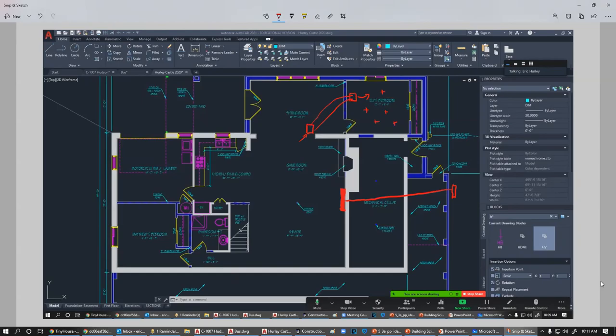All right. So I've got that inch space under here. I do have some air flowing through here, and I do have some air exchanges in here. This is not passive. There's an inline duct fan in here. In the summertime, it comes on every 30 minutes and shuts off for every 30 minutes. In the wintertime, it runs constant just to pull heat in here because this is the basement. Most of it's underground. It's kind of gloomy. So we want to try to get enough heat in here to keep him comfortable.